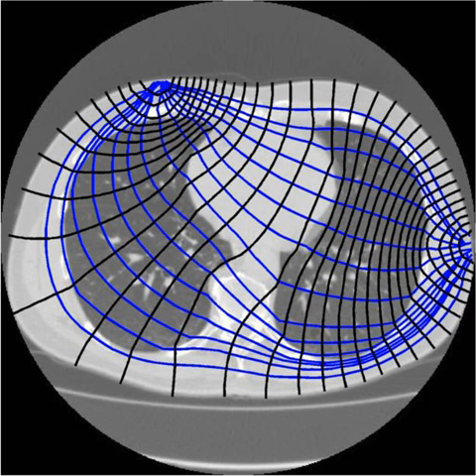The current itself is applied using current sources, either a single current source switched between electrodes using a multiplexer or a system of voltage to current converters, one for each electrode, each controlled by a digital to analog converter. The measurements again may be taken either by a single voltage measurement circuit multiplexed over the electrodes or a separate circuit for each electrode.